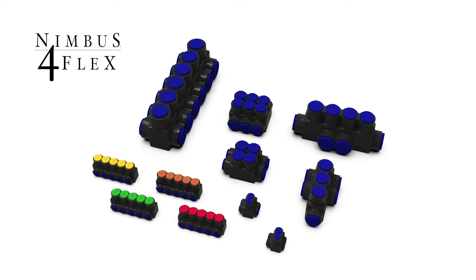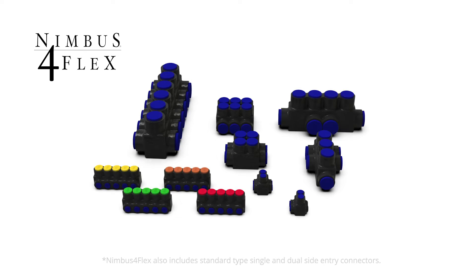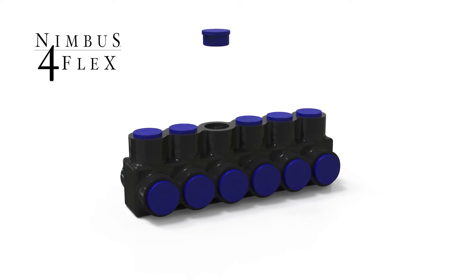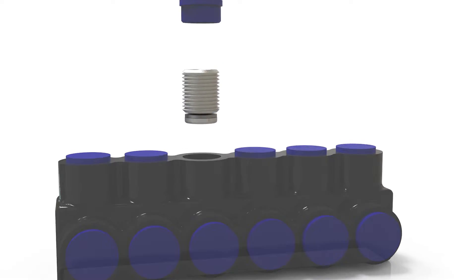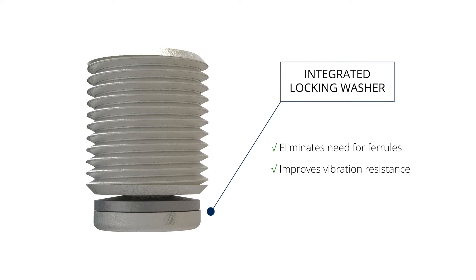The Nimbus4Flex series is flex rated and includes Nimbus for motors, shapes, and our 2X series. Easily identified with blue caps, Nimbus4Flex features a patented screw design. Each screw has an integrated locking washer that eliminates the need for ferrules, improves vibration resistance, and compresses the flexible conductor strands without damage.